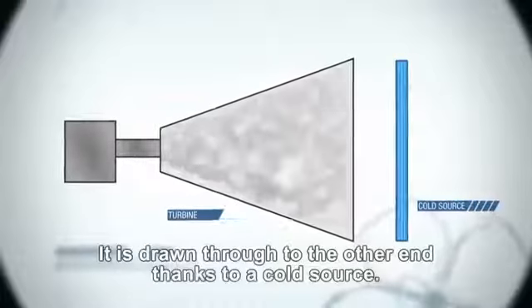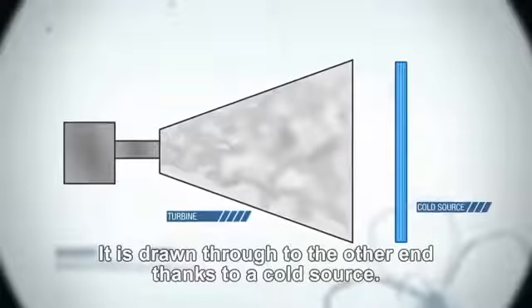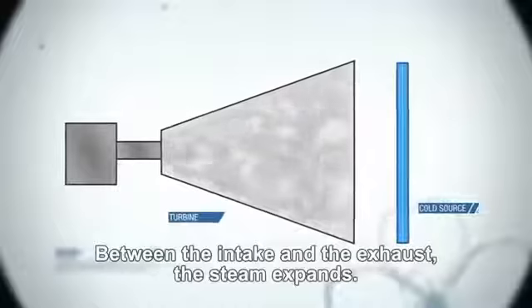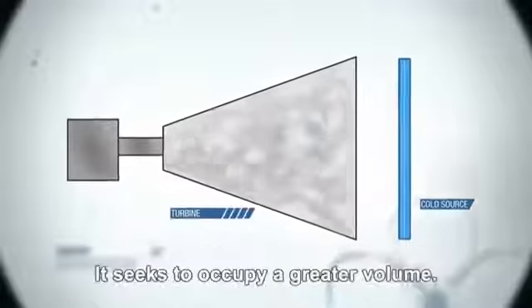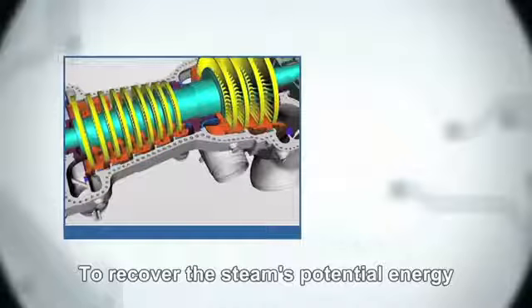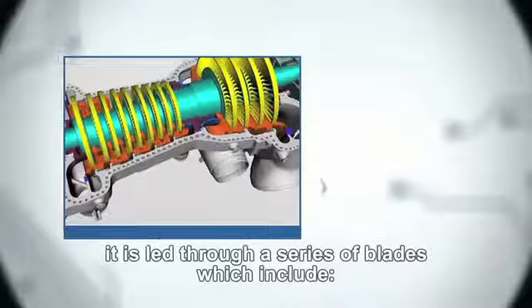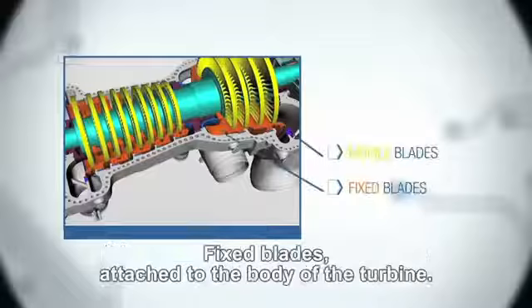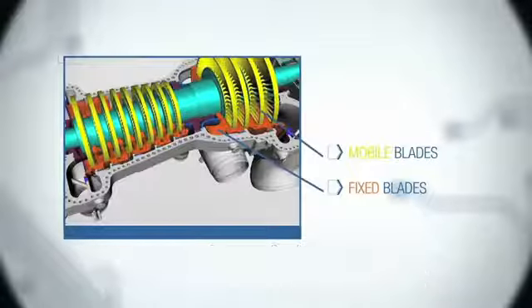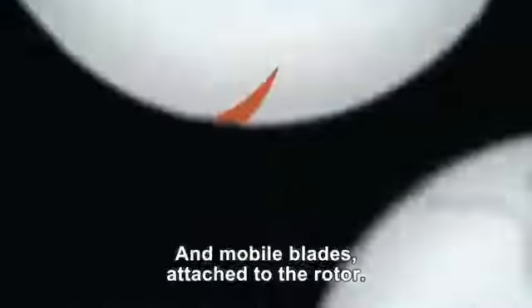It is drawn through to the other end thanks to a cold source. Between the intake and the exhaust, the steam expands. It seeks to occupy a greater volume. To recover the steam's potential energy, it is led through a series of blades, which include fixed blades attached to the body of the turbine and mobile blades attached to the rotor.